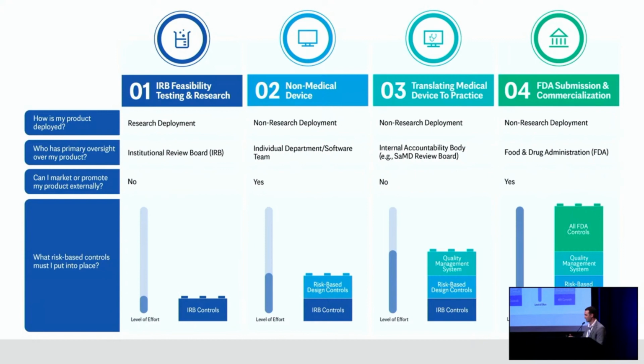Same thing with stage three. If you're a medical device, you're adding a little bit more rigor on that bar column next to it. Maybe you're adding a quality management system to your research and your design controls to get it into a stage that is then ready for the FDA in stage four. And with FDA, you obviously have a lot more controls because you'd be a commercial market, you have reporting obligations, audit obligations, and so forth. So I like to think about it this way so that we don't do ourselves a disservice by doing work that's not going to be useful down the road.